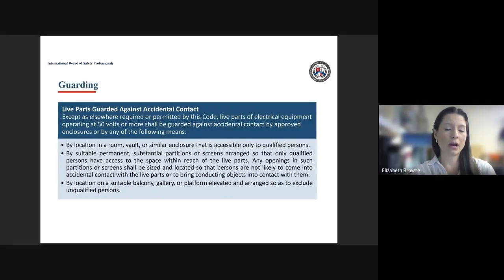All right, so guarding. We always want to guard any live parts against accidental contact. Again, the rule of thumb is any live parts over 50 volts should be guarded against. A lot of control wiring now is 24 volts or less than 50 volts. It certainly would not hurt to guard that as well, but it's only 50 volts and higher that is required by OSHA to be guarded.